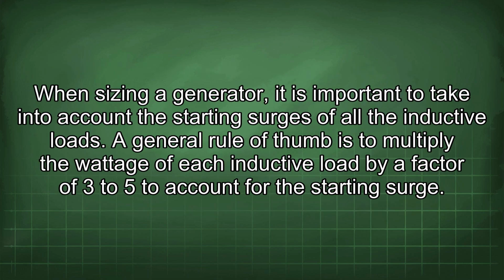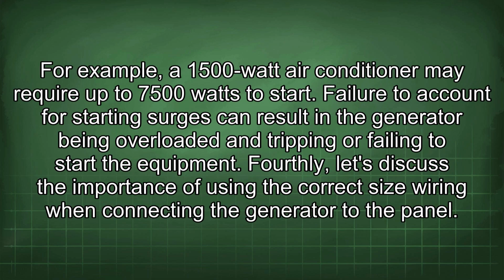When sizing a generator, it is important to take into account the starting surges of all the inductive loads. A general rule of thumb is to multiply the wattage of each inductive load by a factor of 3 to 5 to account for the starting surge. For example, a 1500 watt air conditioner may require up to 7500 watts to start. Failure to account for starting surges can result in the generator being overloaded and tripping or failing to start the equipment.